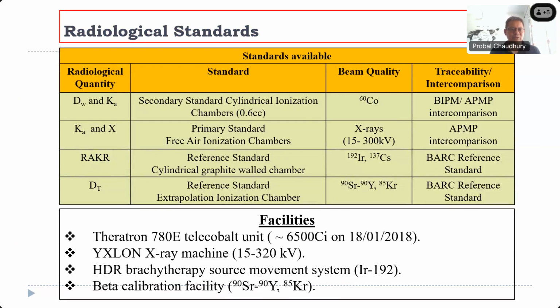This is a table of radiological quantities. The secondary standard for the cylindrical ionization chamber has beam quality cobalt 60, with BIPM and APMP intercomparison. Similarly, for primary standards and free air ion chambers, we carry out X-rays with APMP intercomparison. Then a reference standard for the cylindrical graphite wall chamber, for iridium 192 and cesium 137. These are the BARC reference standards, and reference standards for the extrapolation ion chamber, that is strontium 90, yttrium 90, and krypton 85, are also BARC standards.